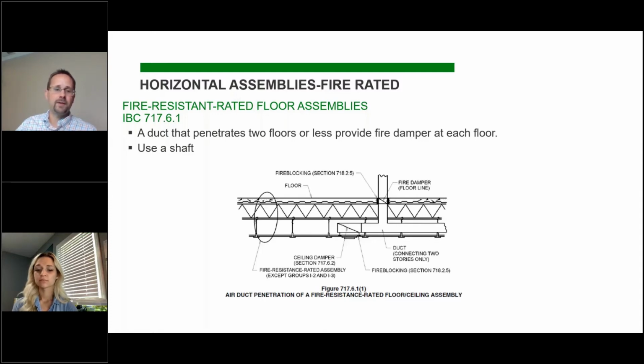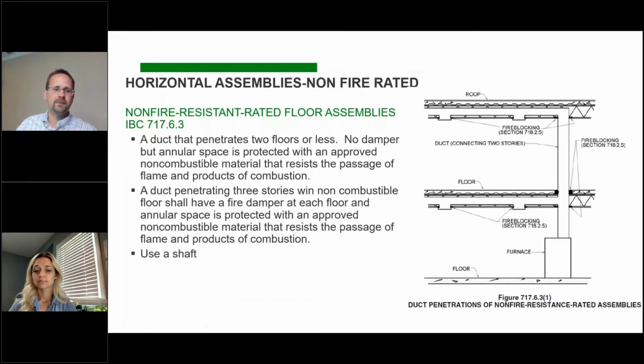But if you have a fire rated floor and you're only going between 2 floors, you can definitely do it without a true shaft if you have fire dampers at each floor. The next one is in section 717.6.3, where it talks about a building that does not have fire rated floors. Now, this doesn't really apply to healthcare, but because we're talking about shaft enclosures, I wanted to include the entire picture. Most healthcare applications would have fire rated floors. But this is just good general information that encases this entire discussion.